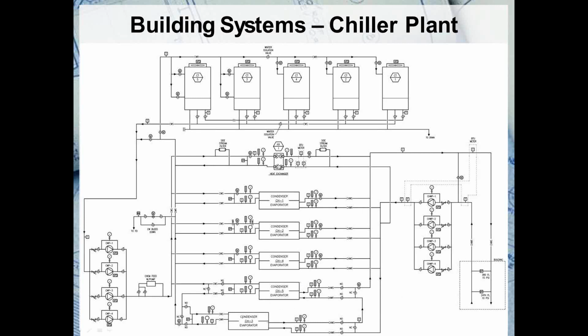They also have a plate and frame heat exchanger for waterside economizer mode used in the winter. They have variable primary chilled water distribution, and these pumps are designed to be 1 pump per 800-ton chiller, or 1 pump per chillers 3 and 5 operating in series counterflow. On the condenser water side, there are 3 variable speed summer towers sized to operate 1 per 800-ton chiller. And there are 2 variable speed winter towers, which are equipped with basin heaters. And these winter towers are programmed with a de-icing mode for use in the winter.